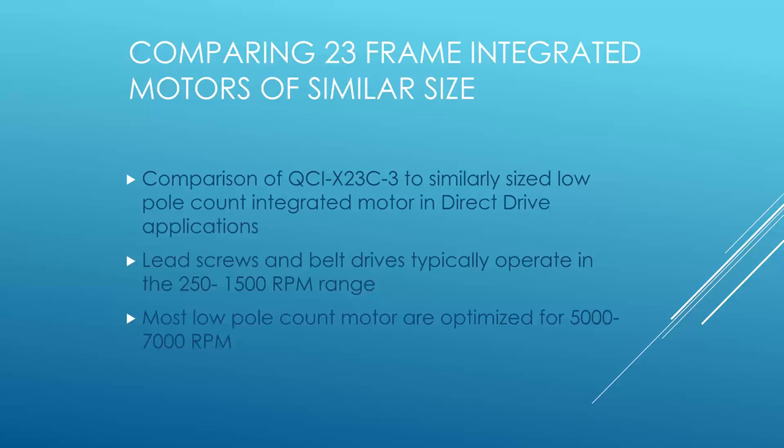I see a question about inertia mismatch. The ratio of the inertia of the rotor of the motor to the load attached to it is called the inertial ratio. When you have a load with a much higher inertia than the motor, that's considered a mismatch. A lot of common servos, with PID for example, want to be around 1-to-1, which is what a lot of people aim for, with no more than about 6 or 8-to-1, beyond which they're not able to prevent the motor from oscillating or operate effectively. Our control system operates a little differently, which allows us a much wider range.